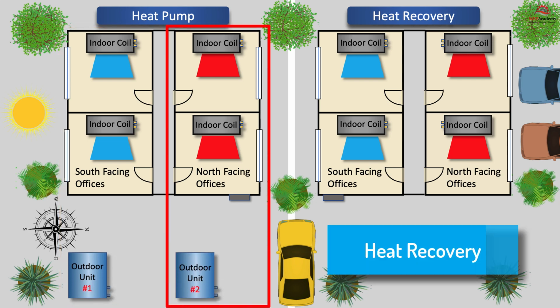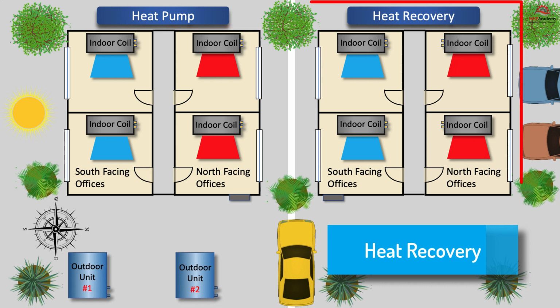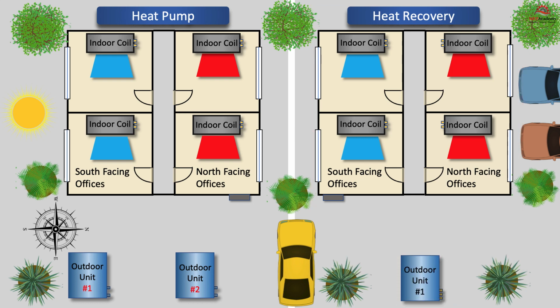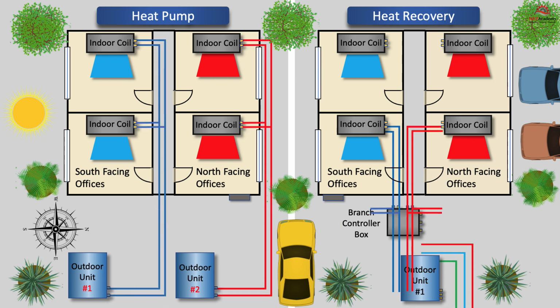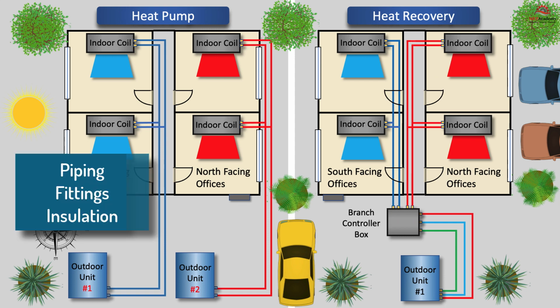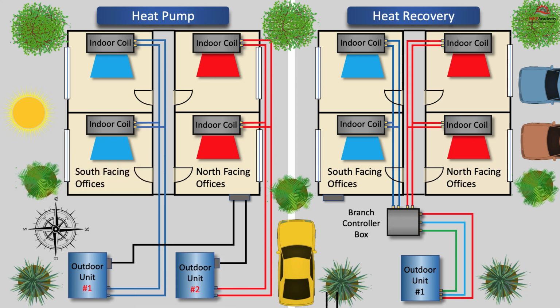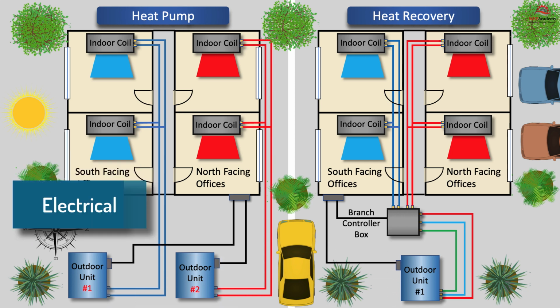The heat recovery system is perfect for this type of balanced zoning and will require only 1 outdoor unit, but will need a branch controller box to route heating or cooling to the indoor units. The total amount of piping, fittings, and insulation costs will need to be determined between the 2 designs. All of the outdoor units and the branch controller will need electrical power.